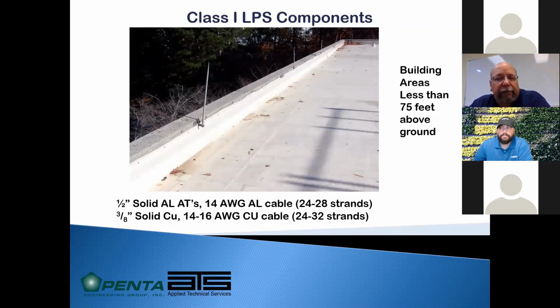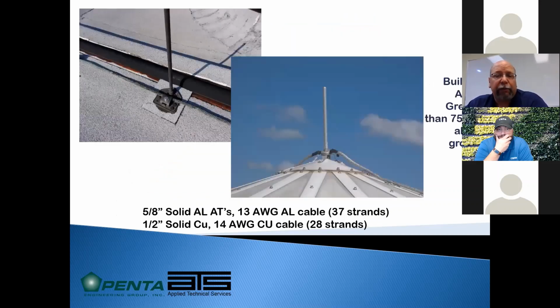There's a difference. As I mentioned, there's copper materials and aluminum materials. Copper is a better conductor, so it doesn't have to be quite as thick to carry the same amount of energy. On a class 1 building that's less than 75 feet, the air terminals will be 1/2 inch solid aluminum or 3/8 inch solid copper. On a class 2 building, aluminum would be 5/8 inch thick air terminals or 1/2 inch thick copper.